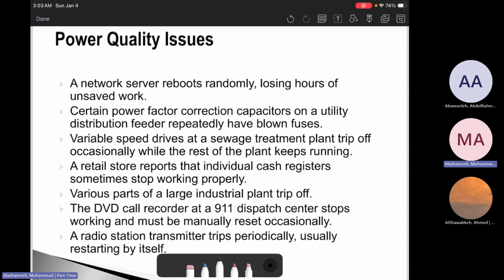The other thing: a variable frequency drive, VFD, trips occasionally, but the rest of the plant runs. Variable frequency drives are very sensitive to DC link undervoltage caused by sags or to control power disturbance. Many drives trip to protect themselves while other loads ride through without a big problem. So if a VFD gets tripped, this can impact the overall system performance. Another example: a cash register stops working properly. Point of sale systems are basically computers. They hate voltage dips and noise. Computers are very sensitive to grounding, to voltage dips, and to noise, which can create a trip or a reboot of the computer.